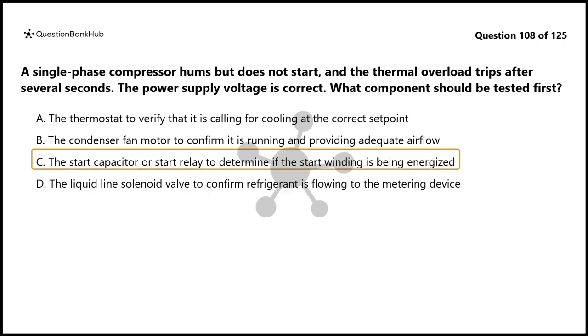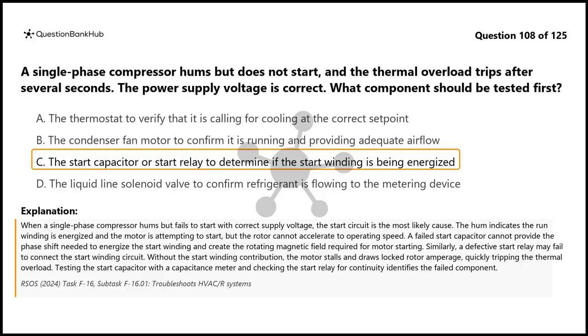The correct answer is C. When a single-phase compressor hums but fails to start with correct supply voltage, the start circuit is the most likely cause. The hum indicates the run winding is energized and the motor is attempting to start, but the rotor cannot accelerate to operating speed. A failed start capacitor cannot provide the phase shift needed to energize the start winding and create the rotating magnetic field required for motor starting.